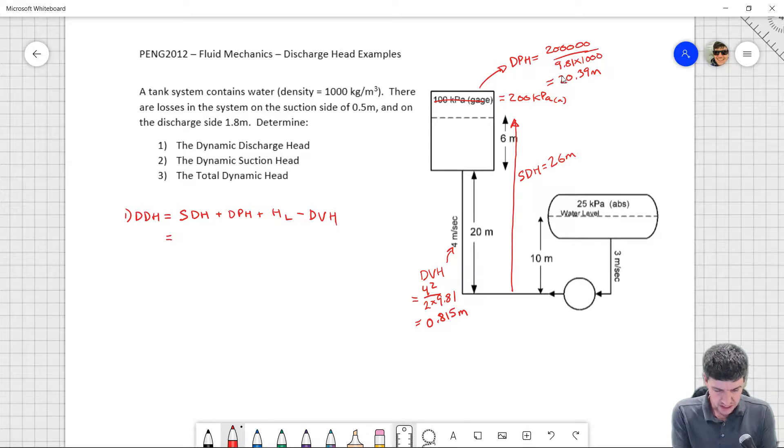Okay, so my dynamic discharge head is going to be my static discharge head 26 meters plus my dynamic pressure head 20.39 meters plus the head loss on the discharge side which was given in the problem 1.8 meters minus the velocity head 0.815 meters. And altogether that gives me 47.375 meters.